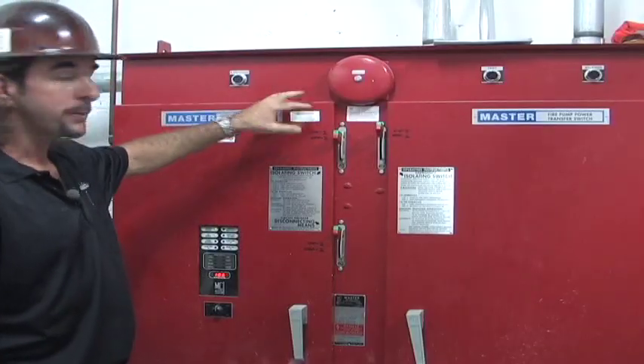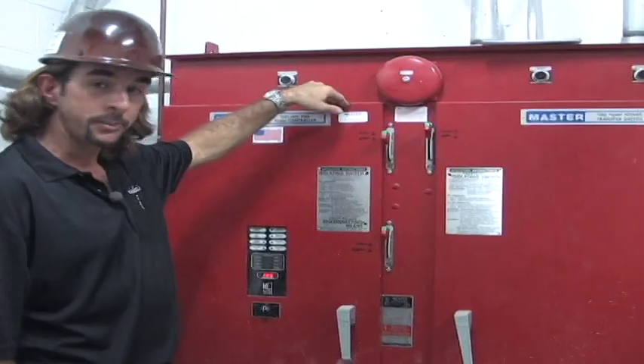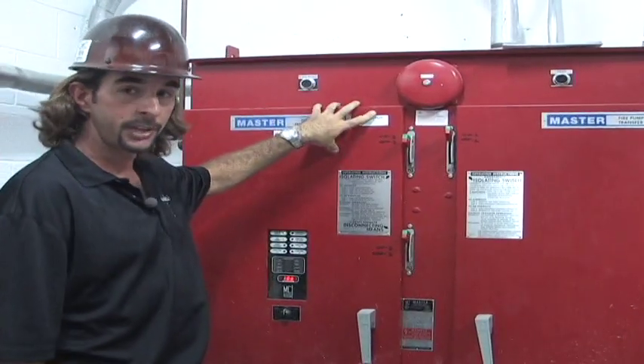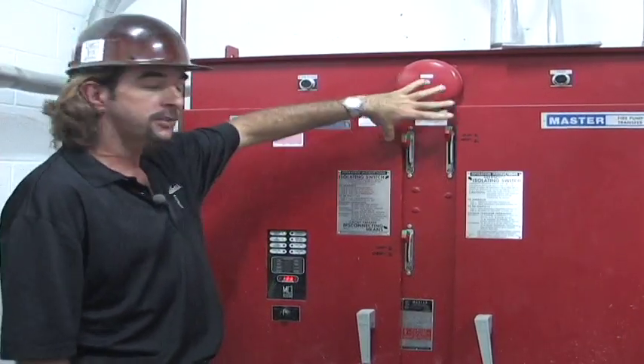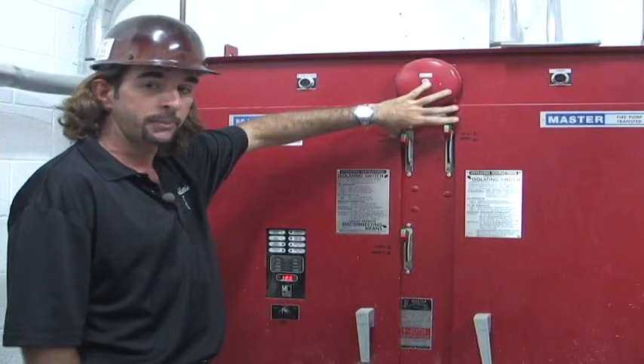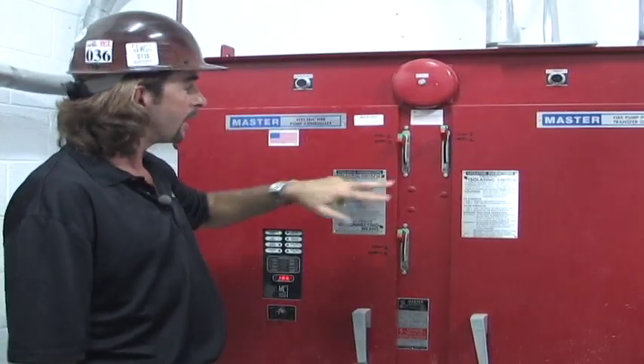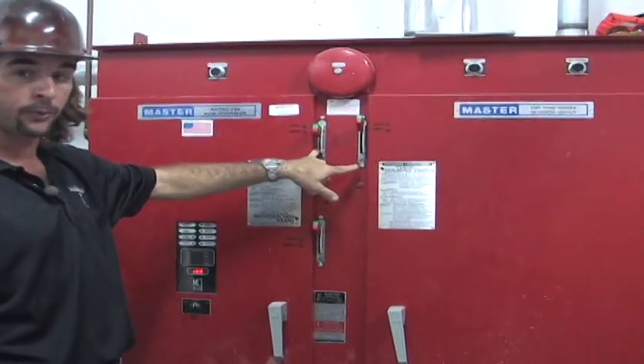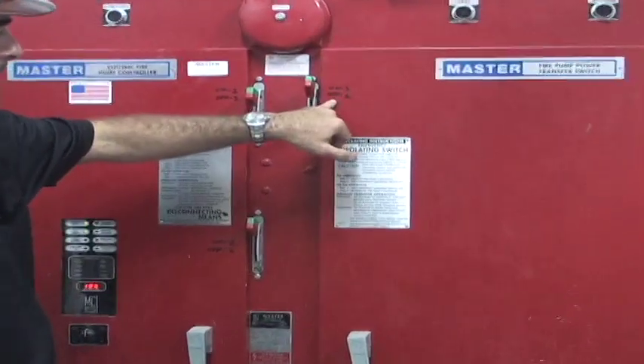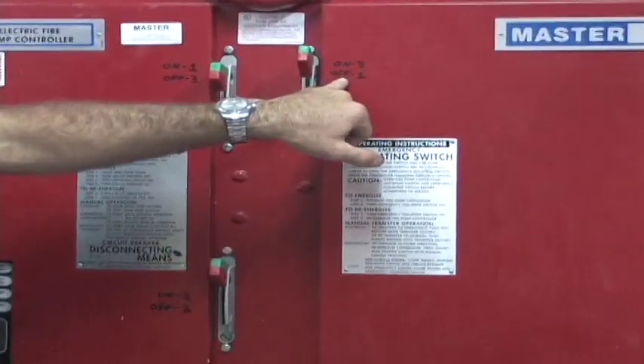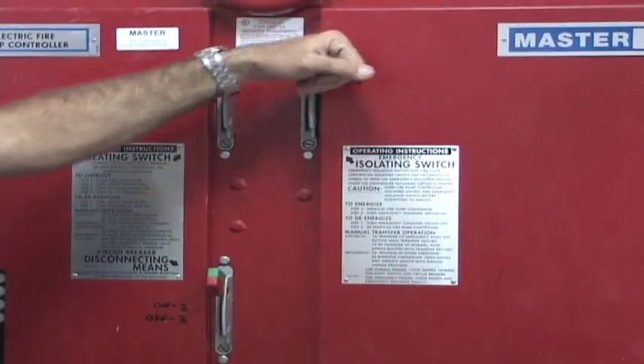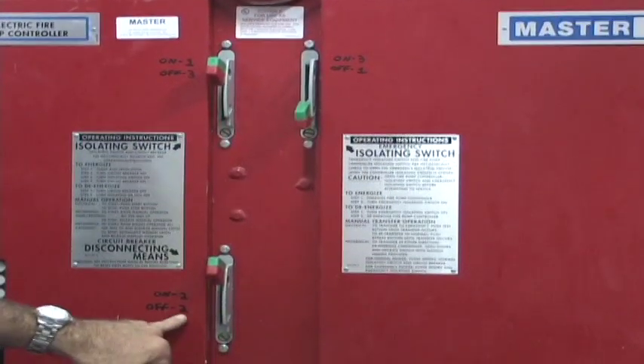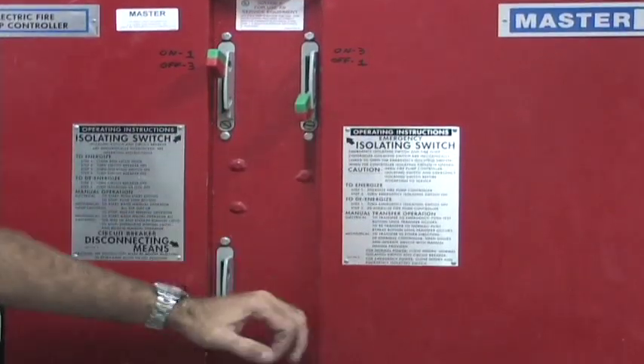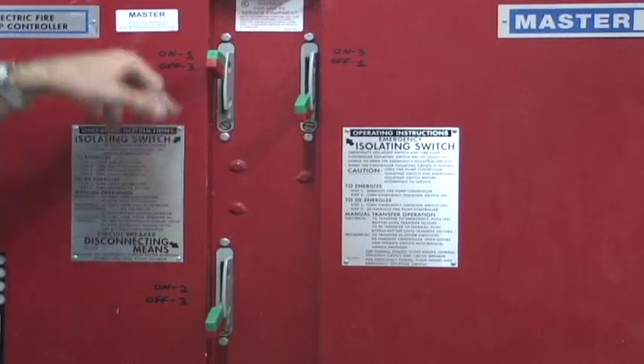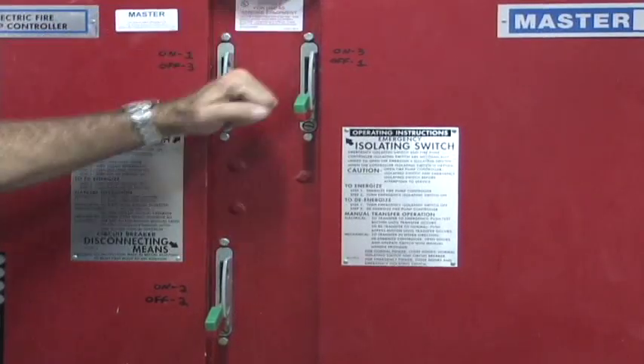Again, on our fire pump, if we needed to shut the power off, if we had to do some kind of service, this is also a 480 volt panel. Any work that should be done beyond these doors should be by a licensed electrician. If we needed to shut this power off for any kind of work on the fire pump, we have it on the sides. For the off position, we're going to shut this one off first. We're going to shut this one off second, the disconnecting means. And then third, we're going to shut off the isolating switch.